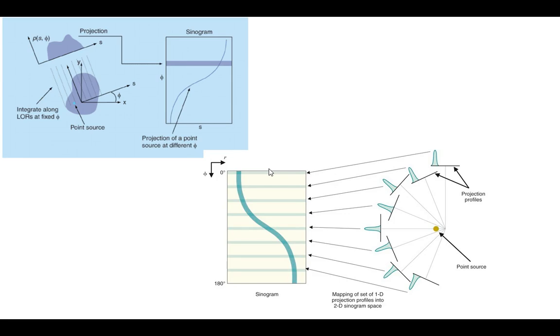Here it's assuming that we've got, in essence, parallel rays coming in. It's really not significantly different when we go to fan beam geometry or cone beam. So just imagine that I'm taking these. It's going to integrate all of those attenuation coefficients along the path, and we're going to get a net amount of loss. That's the shape showing up there on the projection. So you've got the source on the bottom part going through lots of attenuations along the length, and where it's thicker, more gets attenuated. Make sense?